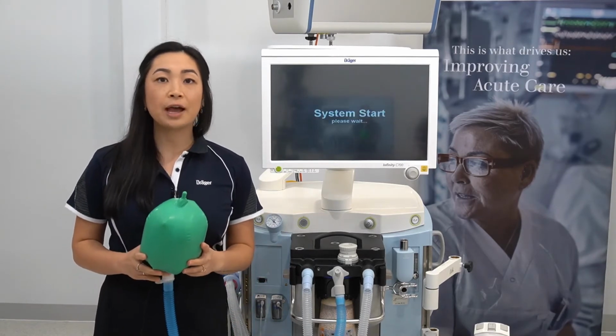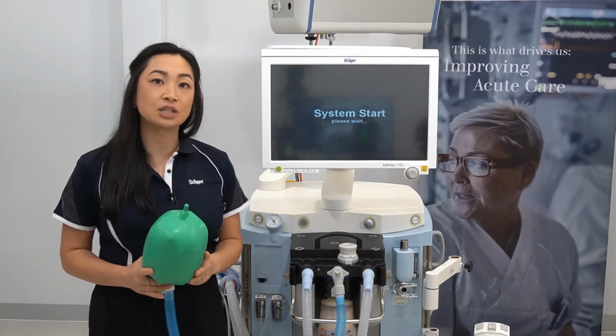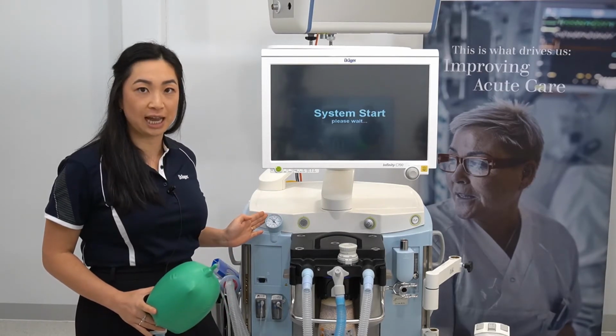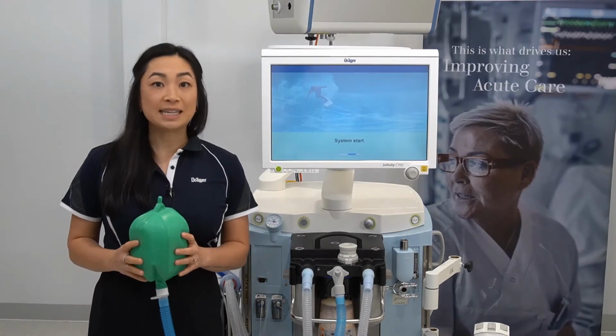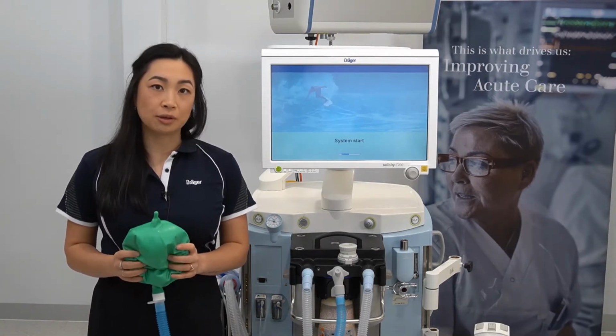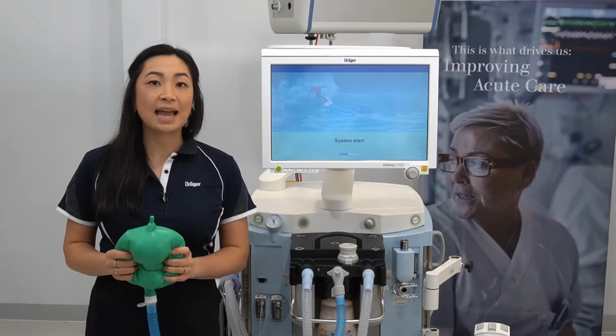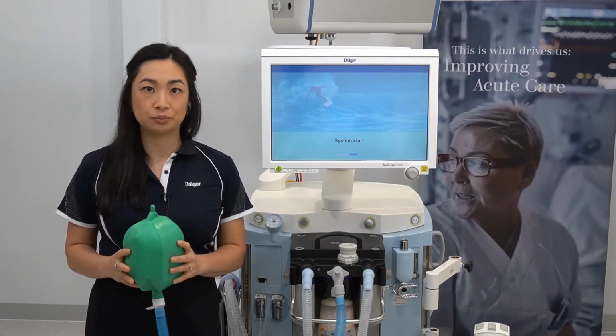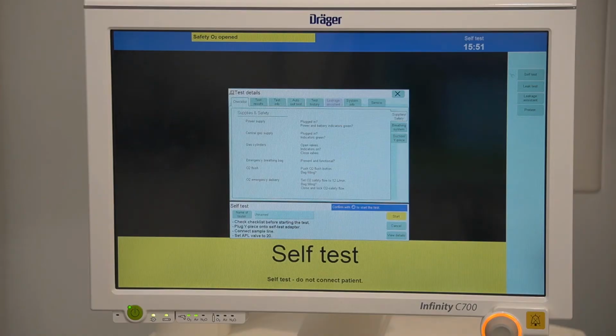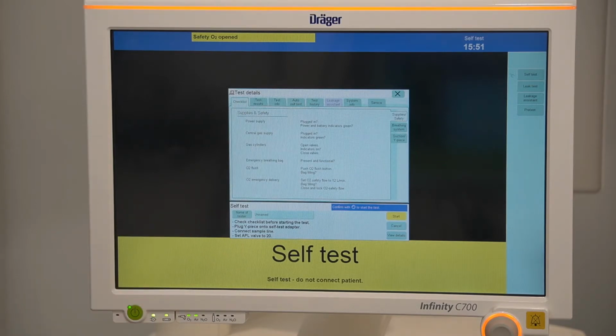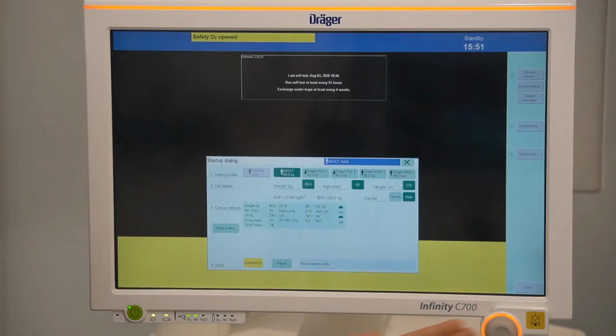You can verify your patient's airway pressures at this time against the manual pressure gauge. Your DIVA metering modules are unavailable at this time, therefore anaesthetic agent delivery is not possible. Your device will power up to this screen seen here, which is the system test checklist. To bypass this, select cancel, confirm with the rotary knob. Then you can start in manual spontaneous mode by confirming.